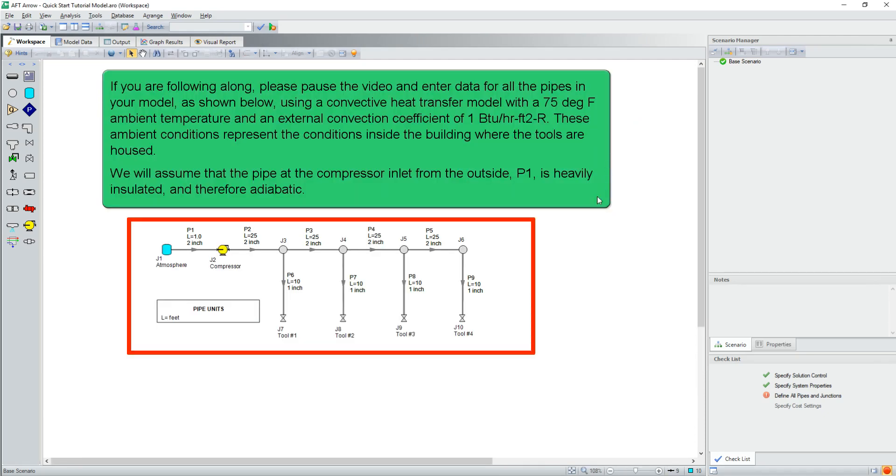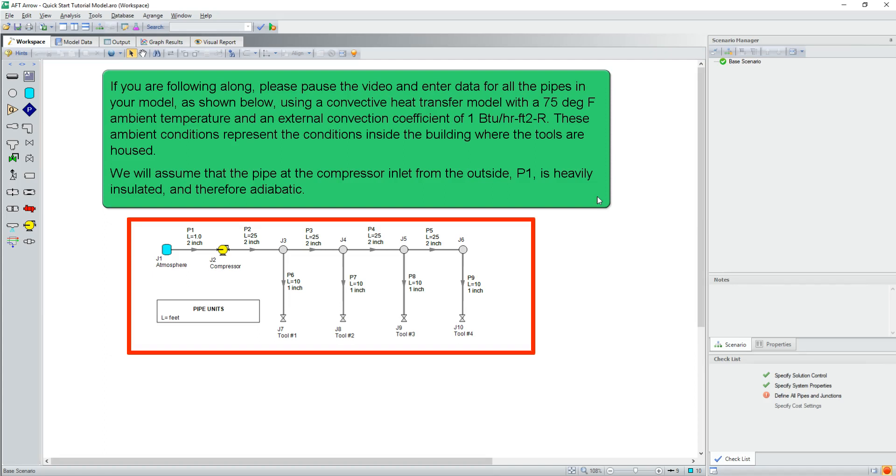If you are following along, please pause the video and enter the data for all the pipes in your model as shown below, using a convective heat transfer model with a 75 degree Fahrenheit ambient temperature and an external convection coefficient of 1 BTU per hour foot squared rankin. These ambient conditions represent the conditions inside the building where the tools are housed. We will assume that the pipe at the compressor inlet from the outside, P1, is heavily insulated and therefore adiabatic.